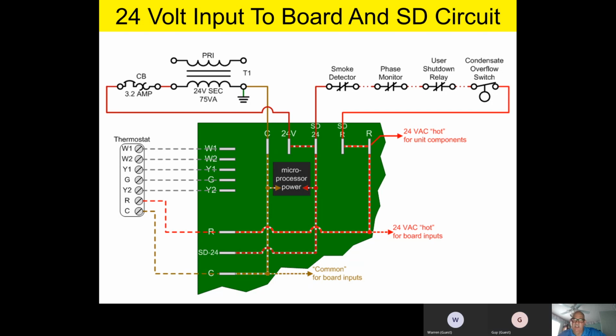Another little side note, if you're getting erratic operation, there's three things I want you guys to remember. If you're getting erratic operation, says the SD circuit is open. Gee whiz, how come there's nothing on the SD circuit? The first and foremost, that circuit has to be closed electrically in order for the unit to work. So you have to have a solid physical electrical connection between SD24 and SDR in order for the unit to work. Now, the microprocessor will still be alive, but the unit will be dead. And so just kind of keep that in perspective.